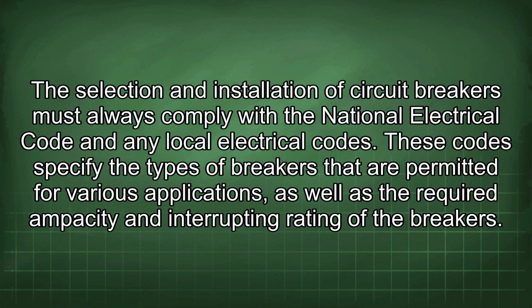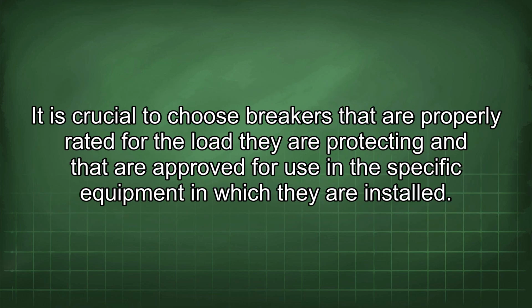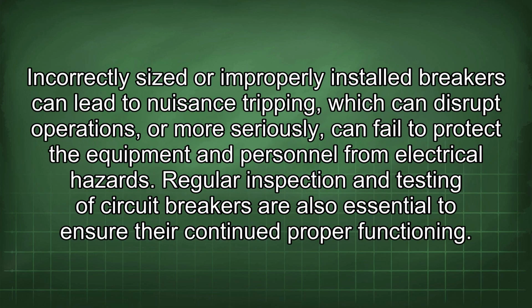These codes specify the types of breakers that are permitted for various applications, as well as the required ampacity and interrupting rating of the breakers. It is crucial to choose breakers that are properly rated for the load they are protecting and that are approved for use in the specific equipment in which they are installed. Incorrectly sized or improperly installed breakers can lead to nuisance tripping, which can disrupt operations, or more seriously, it can fail to protect the equipment and personnel from electrical hazards.